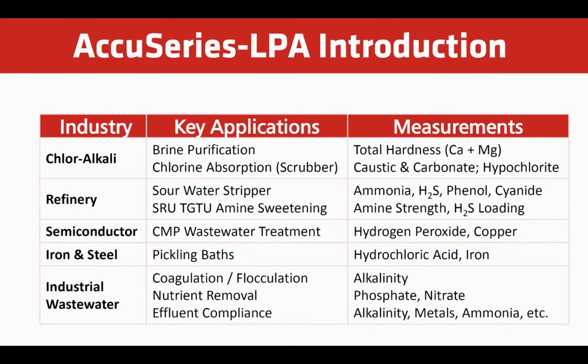In refinery, we do an awful lot of applications in the sour water stripper, so we can measure ammonia, hydrogen sulfide, phenol, cyanides. In the SRU, or tail gas treater unit, amine sweetening, we offer the amine strength and H2S gas loading. In semiconductor, we do an awful lot in the CMP wastewater treatment area of the plant, measuring both copper and hydrogen peroxide value prior to going to municipal sewer.